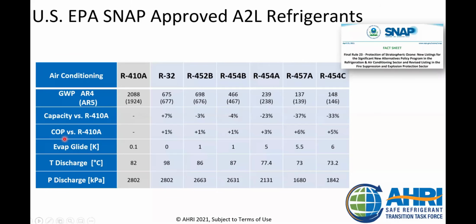COP, which is the efficiency, both of these choices are like one tiny tick better than 410A, like not even enough to get excited. Like what used to be a 15.2 SEER unit might be like a 15.3. It's not a big deal, but it's better, okay, right? There is evaporator glide on everything except R32. All blends have an evaporator glide. That just means that the two refrigerants have different boiling points. So theoretically, if you have a leak, specifically in the evaporator where the refrigerant's converting over to a vapor, one could leak out at a faster rate than another.